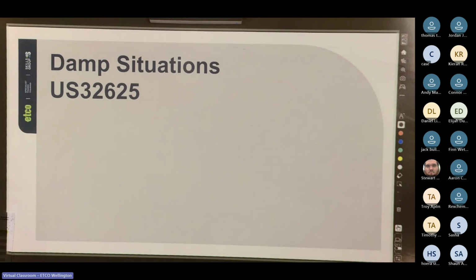Let's move into Unit Standard 32625, damp situations. We're taking the knowledge we talked about on earthing into damp situations. When you're standing barefoot in a bathroom or by a pool, even a small voltage can be lethal. That's why AS/NZS 3000 gives us strict rules on zones, IP ratings, and bonding. Today, we'll start by looking at how damp zones are defined, and we'll talk a bit about the IP index and what that tells us about what equipment can safely be installed. And remember, don't use the toaster in the bathtub.